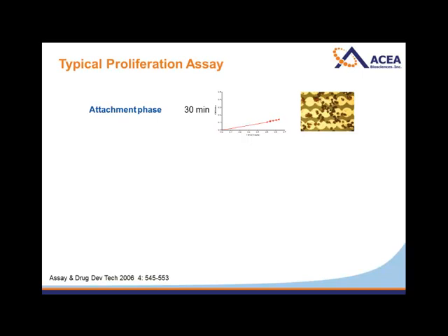What we typically do then, I already mentioned we put the cell growth media in there. Software automatically takes a reading. You set that to 0, so you don't want to worry about differences in different media. Then we'll add the cells. We'll typically wait 30 minutes. That gives the cells time to settle and begin attaching to the biosensor. That ensures a nice, even distribution of the cells across the array. Remember, I mentioned that we're averaging the impedance across the electrode array. So if you have anything that causes the cells to kind of move around and maybe move to the edges, like heating of that column of liquid unevenly, you can actually affect the data quality.